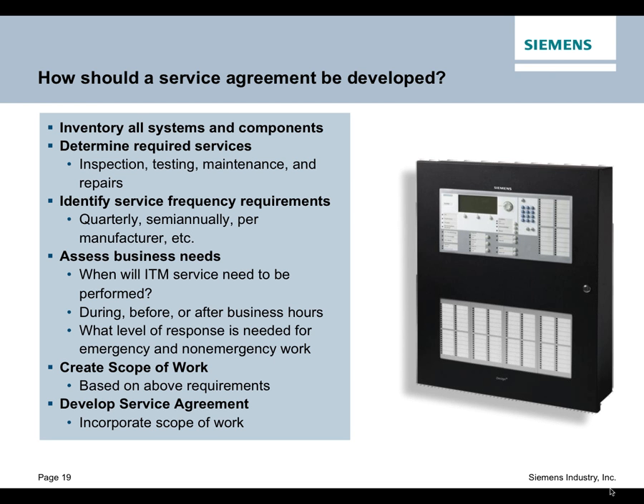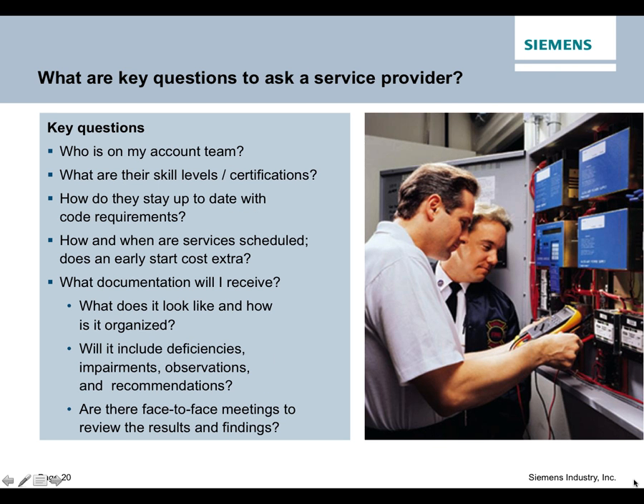When we're doing voice communication systems, voice evacuation systems in buildings, sometimes those can be arranged so that the testing coincides with a fire drill that building safety or building risk management wants to run. So sometimes it's coincided with the fire alarm testing so that both happen at the same time. Other times, we don't want people to be bothered. You've got to come in between 12 midnight and 6 o'clock in the morning to test the voice evacuation system. All of this should be spelled out as part of that plan we talked about and part of the checklist we need to follow. So that's just a checklist for yourself there.